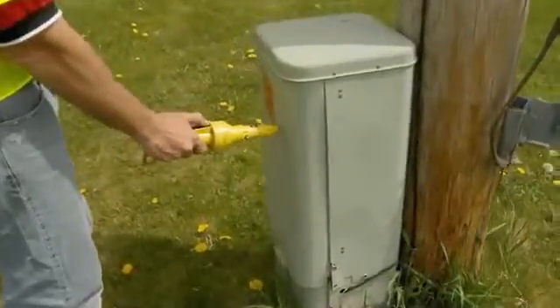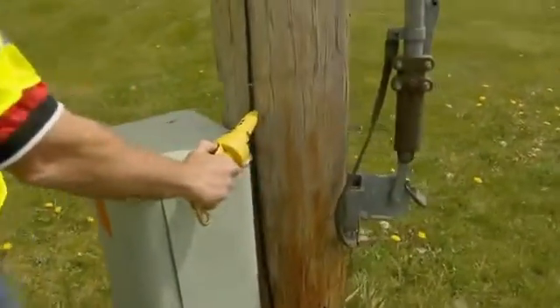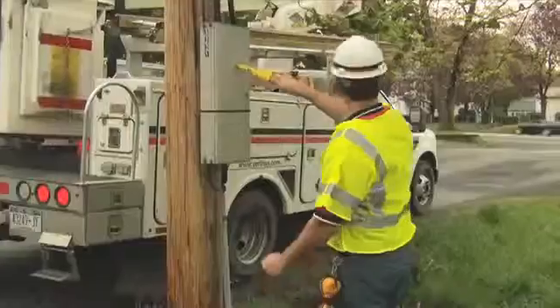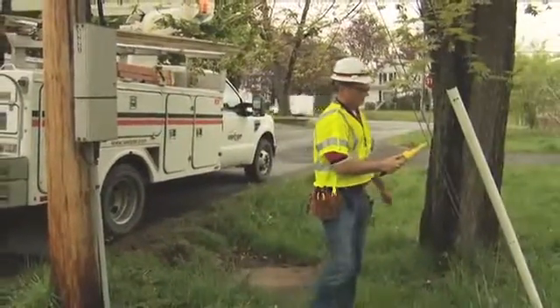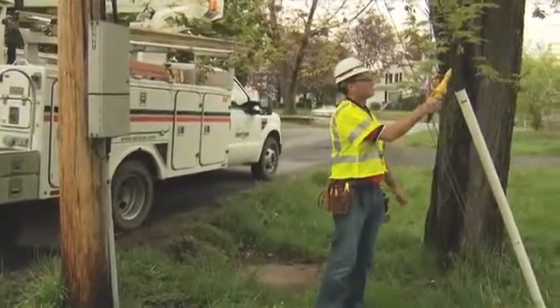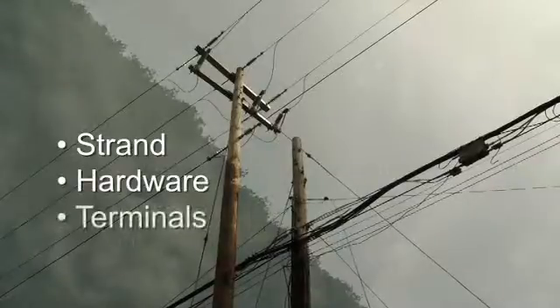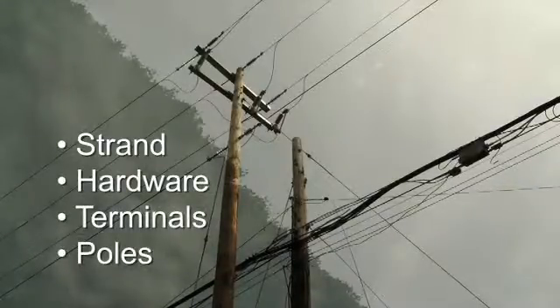Your voltage detector is your best friend and must be used on every job on anything that could be energized. And don't forget that tree limbs and guys can move after you've tested them, so retest if necessary. On joint use poles, you need to test all objects in the workspace: strand, hardware, terminals, poles, and bond anything that could become energized. Here are some other clear examples of hazards.